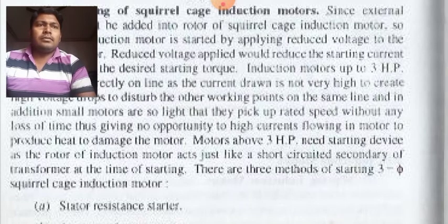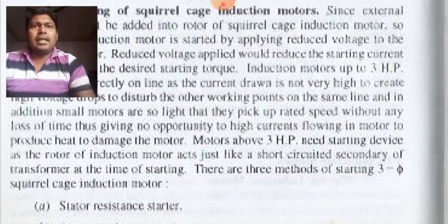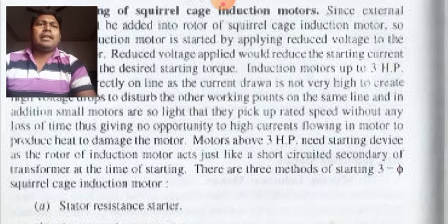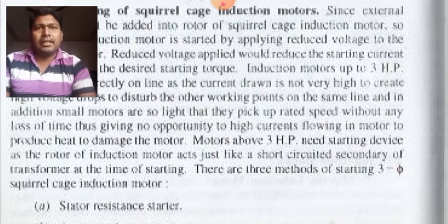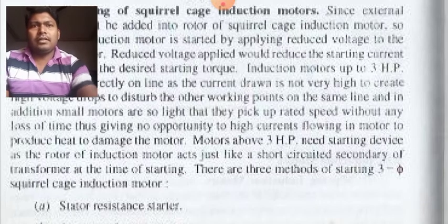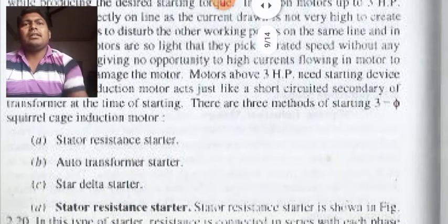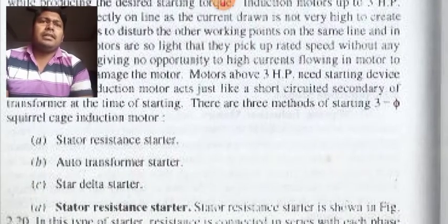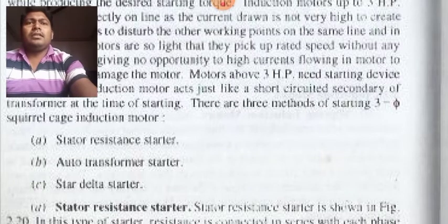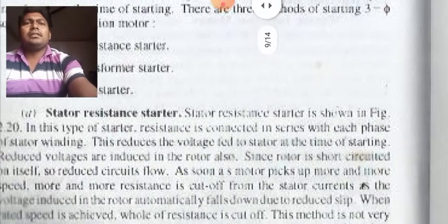It needs a starting device because the rotor of an induction motor acts just like a short circuited secondary of a transformer at the time of starting. There are methods of starting a 3-phase induction motor. So what are the methods? Stator resistance starter, auto transformer starter, and star delta starter. So we will discuss now the stator resistance starter.